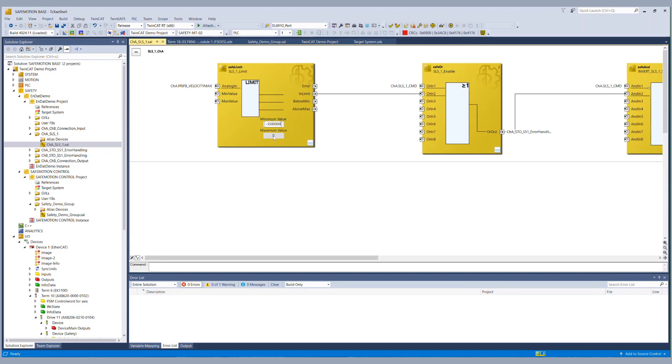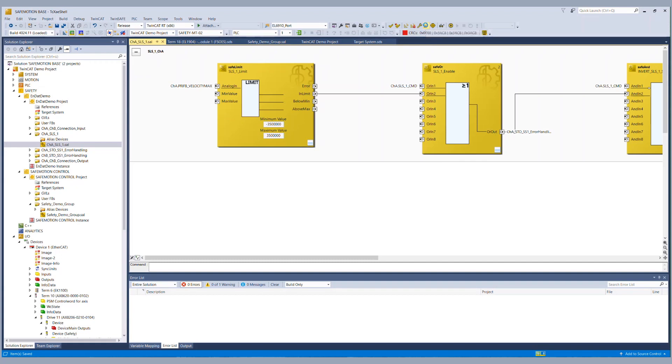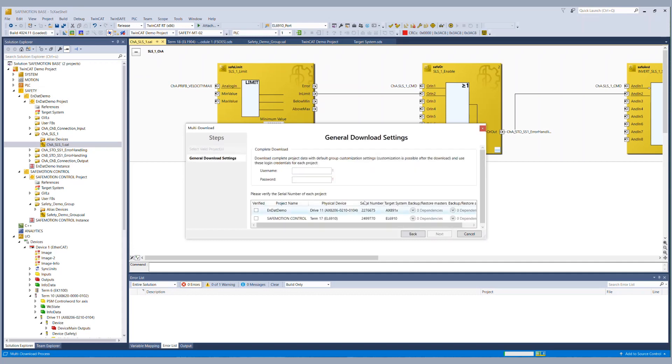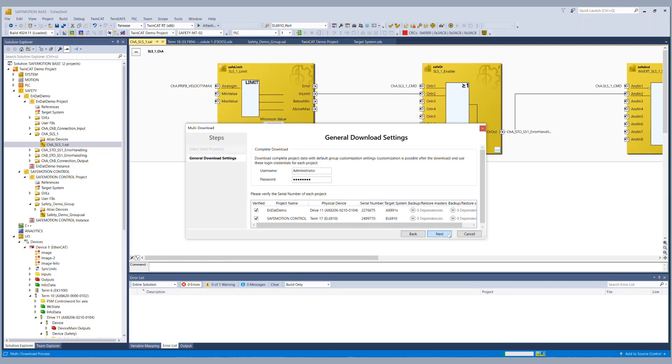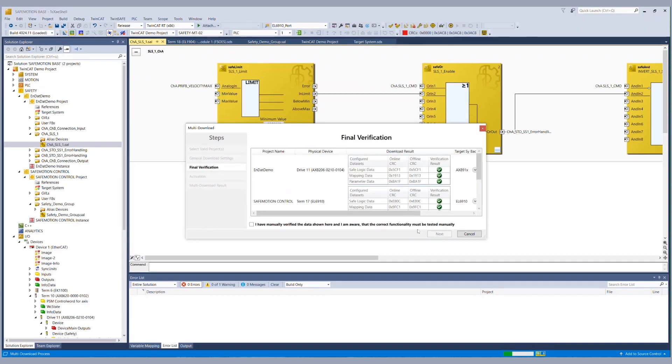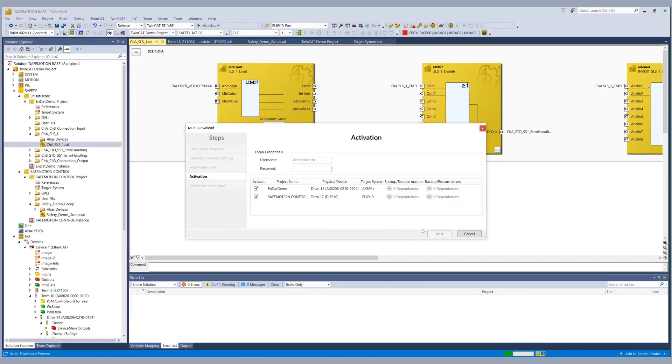And basically now our safety function SLS with an EnDat 2.2 safety encoder is done. So we start the multi-download to get the system running we enter the username and our password. We verify the serial numbers and start the download after the download is finished. We verify the CRCs and enter the password again to activate both project in our case.